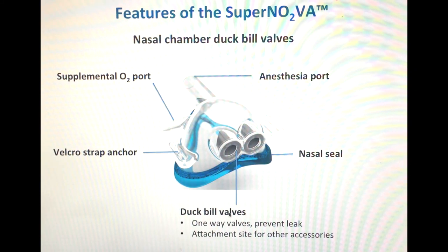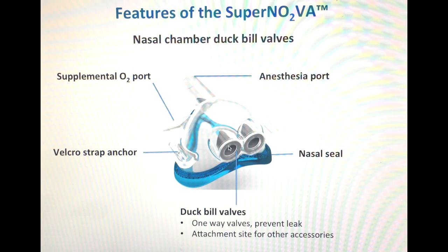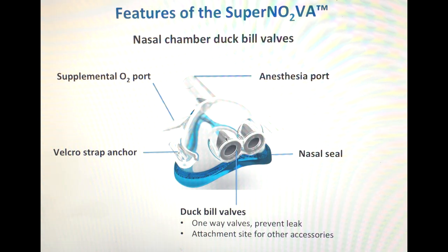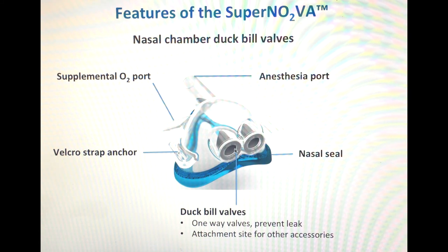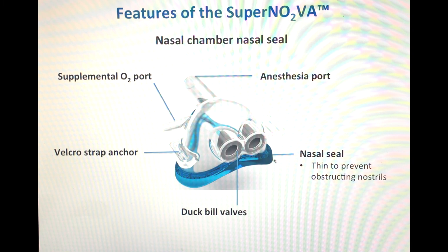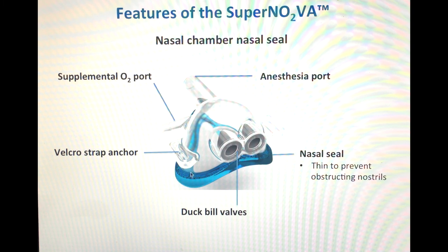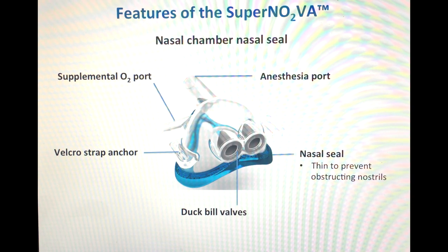The next unique feature is the nasal chamber's duck bill valves, which serve two functions. First, they are one-way valves — when you try to exhale against them, they close. If you insert something such as the oral chamber into the duck bill valves, they open and allow for bilateral flow. The second function is that they act as attachment sites for other accessories. The nasal chamber seal is also uniquely thin, unlike typical anesthesia masks which have a thick balloon seal, so that it doesn't contact the nares and block airflow going into the nose.